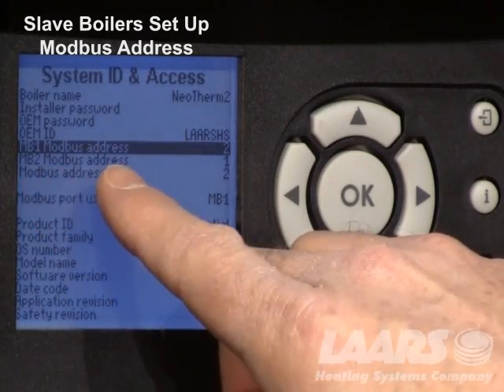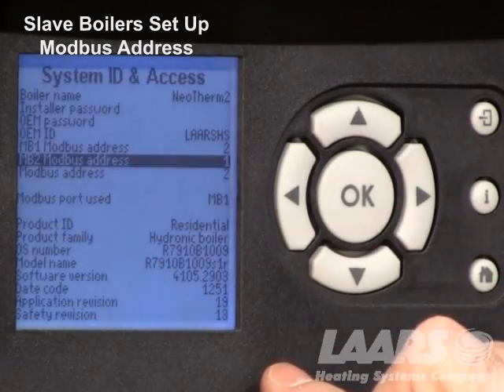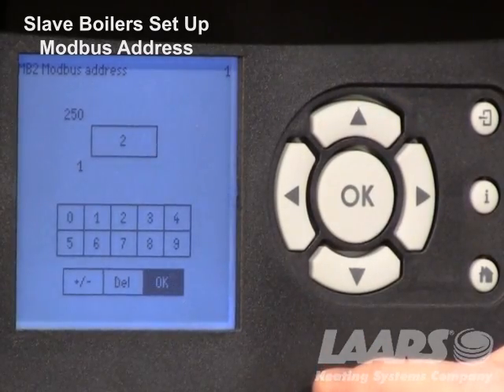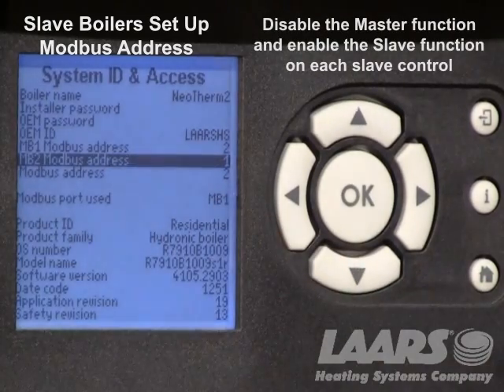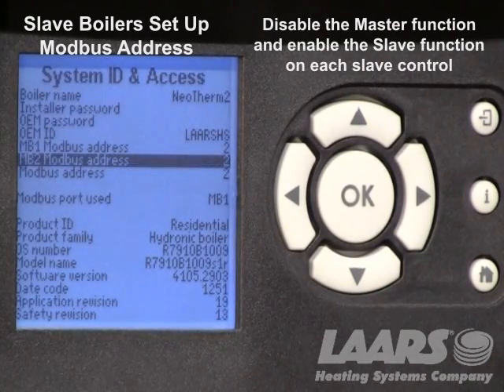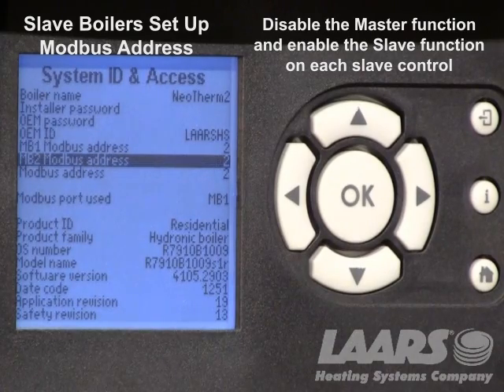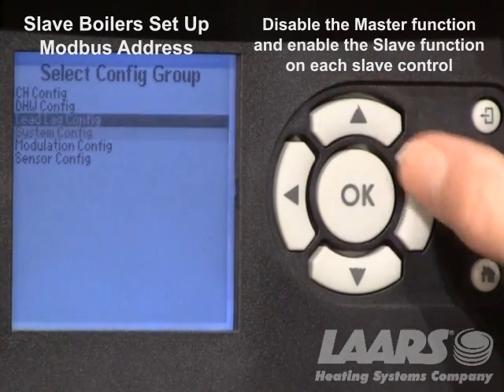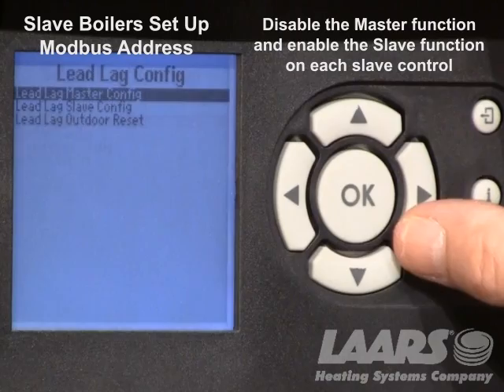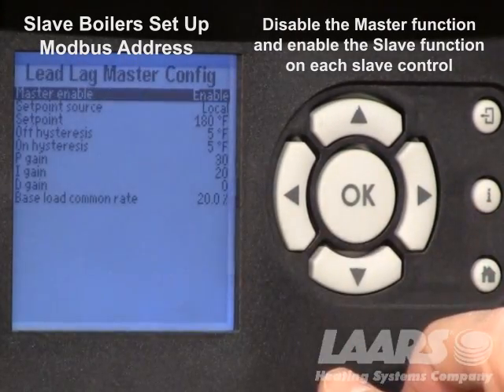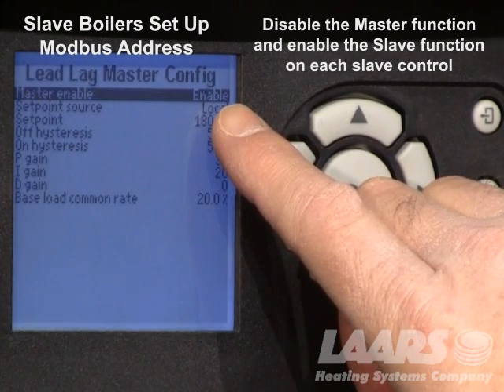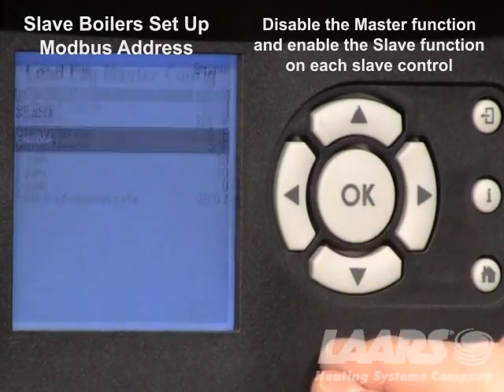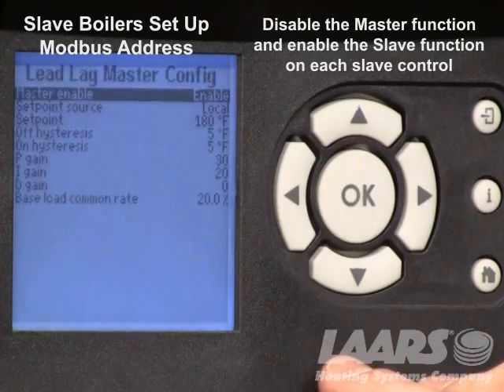We still have the MB2 address — that will need to change also. Go down and highlight MB2 Modbus address, press okay, use the up arrow, choose 2, and press okay again. Now that we've changed the Modbus addresses, go back to the information button, highlight advanced settings, go to lead lag configure, highlight it, press okay, and choose lead lag master configure. On the slave or lag boilers we need to disable the master function. Make sure it's highlighted, press okay, choose disable, press okay again, and it will change. The master is now disabled on the lag boilers.